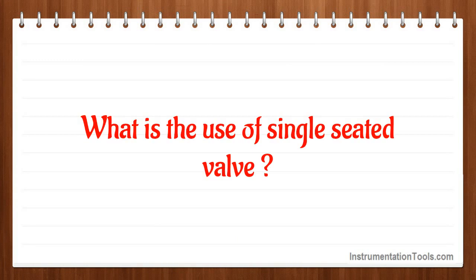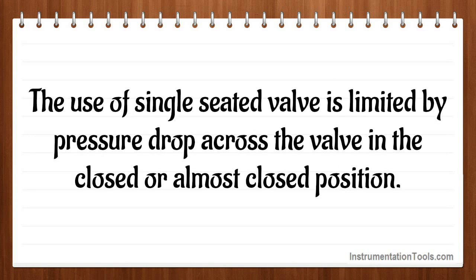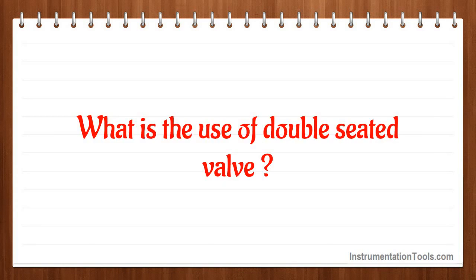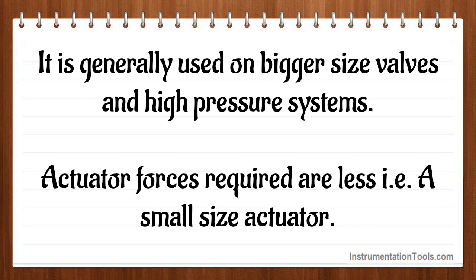What is the use of a single seated valve? The single seated valve is used on smaller sizes and in larger sizes where an absolute shut off is required. Its use is limited by pressure drop across the valve in the closed or almost closed position. What is the use of a double seated valve? In double seated valves, the upward and downward forces on the plug due to reduction of fluid pressure are nearly equalized. It is generally used on bigger size valves and high pressure systems, and actuator forces required are less, allowing a small size actuator.